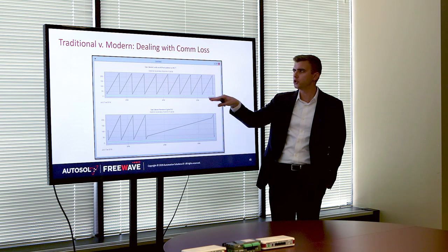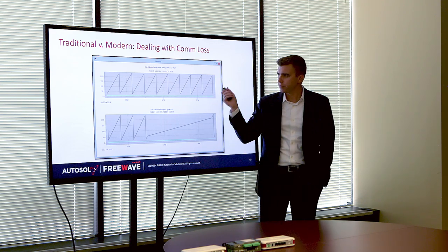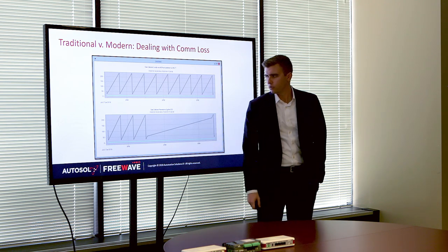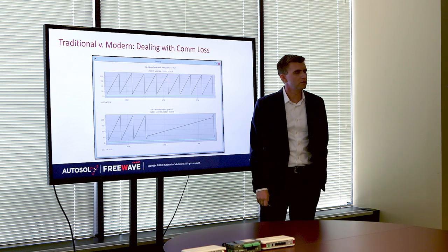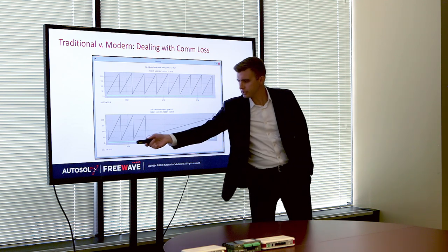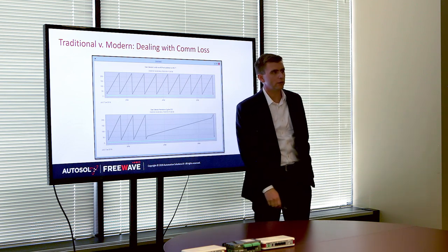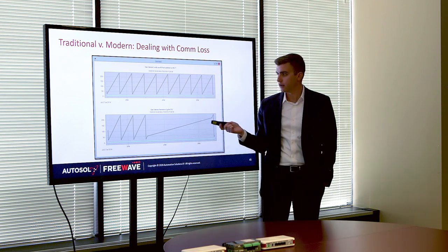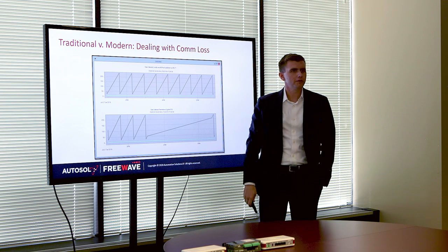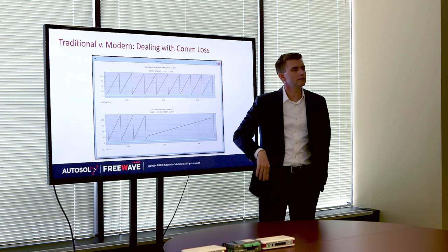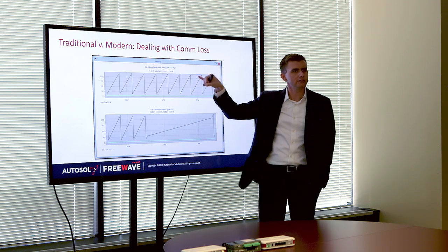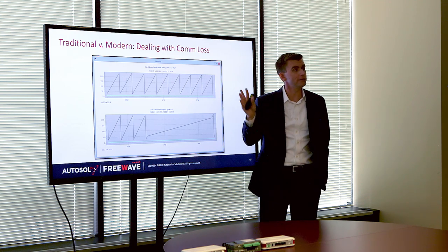The top is data brought in with Edge ACM directly into Cygnet; the bottom is Cygnet's built-in poller. There was an outage on site. The gray zigzag was some kind of heartbeat, and the teal line on both was an ESD point. During this two-hour span, operators were blind. But once communications were reestablished and Edge ACM backfilled the data, all of that data was ran through as real-time data. So if there was an ESD trigger, an operator would have gotten the alarm saying something happened during this time period.